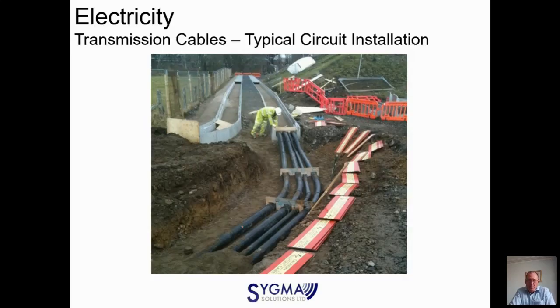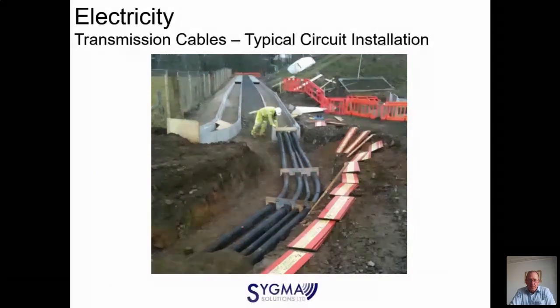So with certainly transmission and even down to 11 kV in some cases, you'll see pilot cables. Pilot is like a comms cable. It's monitoring things like oil pressure, switchgear, all kinds of stuff. So in simple terms, it's like an alarm cable. So wherever you see high voltage cables, you'll very often see pilot cables alongside it. I mean, that is just going to trace as a bank. You're going to struggle to get those individually, unless you guys know something I don't.